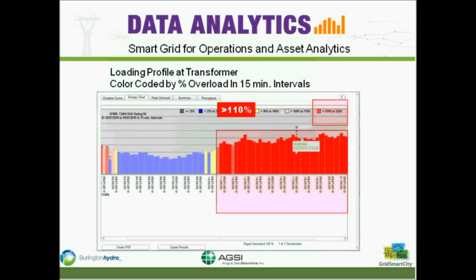Which means the transformer isn't getting a chance to cool down. We can even see when an outage flag came through. This O, I think in the Elster system, stands for outage, R stands for restoration, and T stands for time reset on the concentrator and the meter.